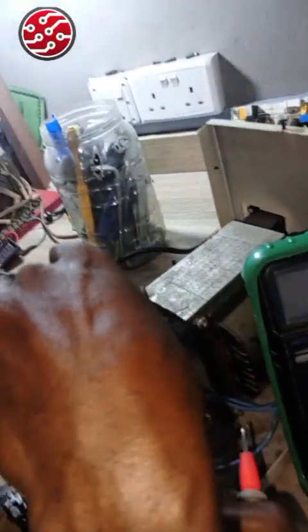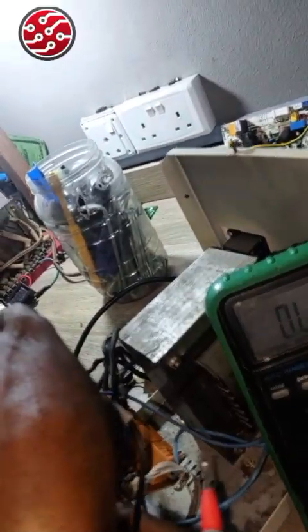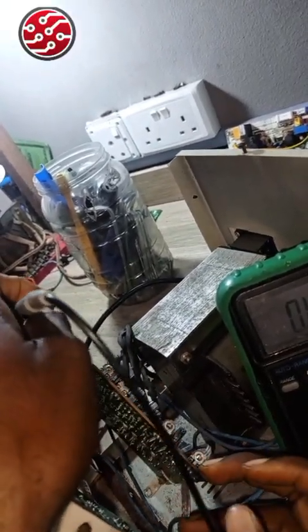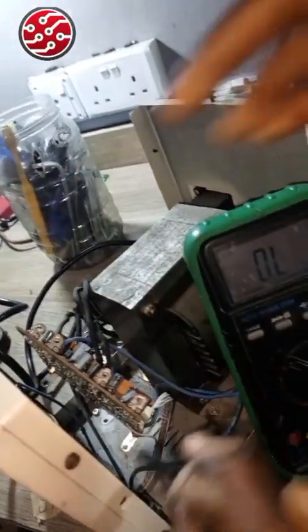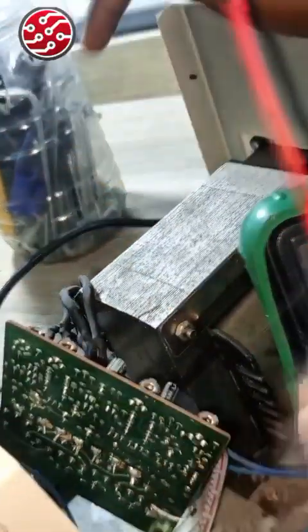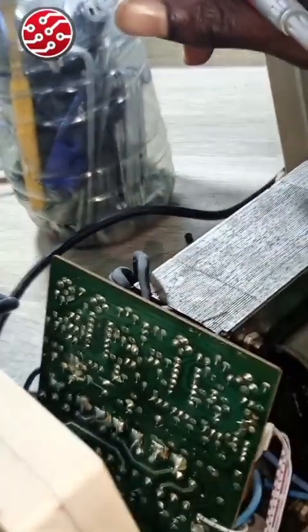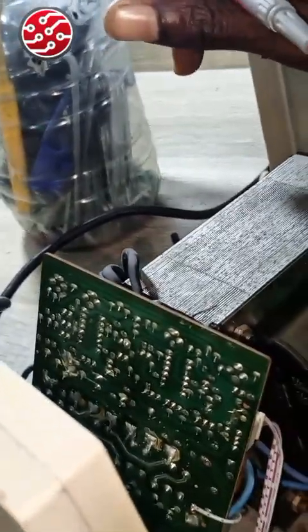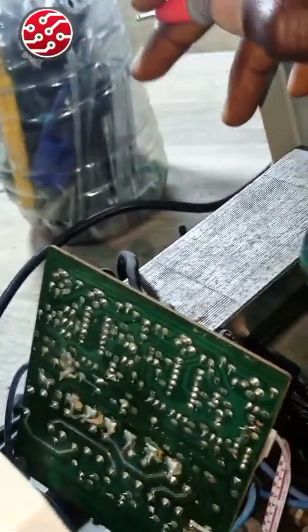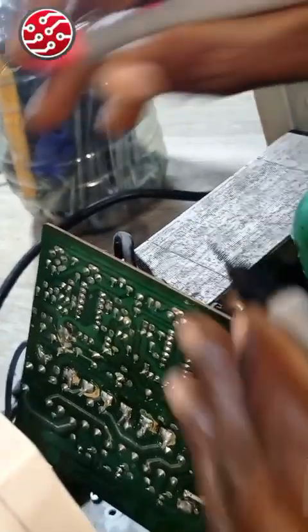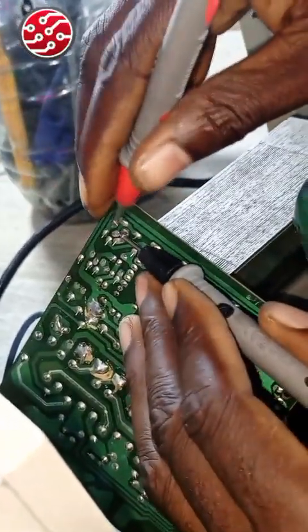107 something K. By the way, let me check the variable first. It's supposed to be either 5K or 10K. When I read it, if your variable is good, and it's 10K, your reading is supposed to be less than 10K, at any angle. If it's anything higher than 10K, remove that variable, it's wrong. So let me check this one.